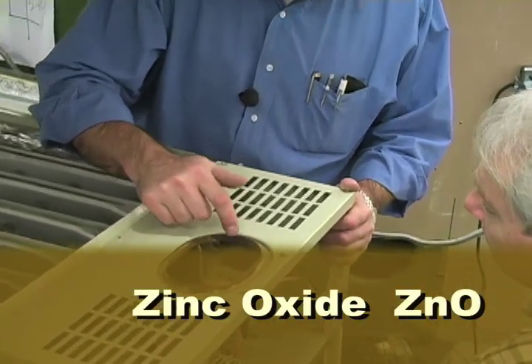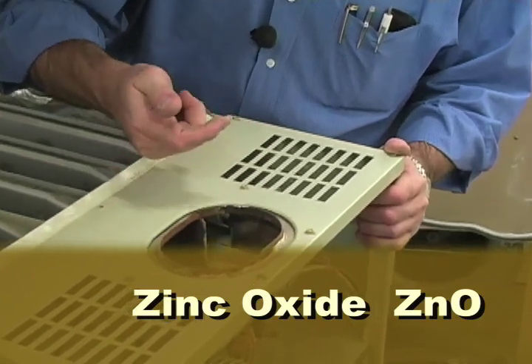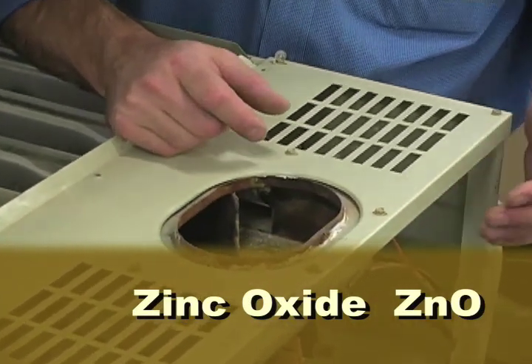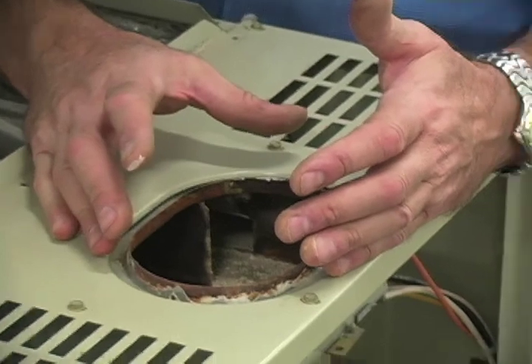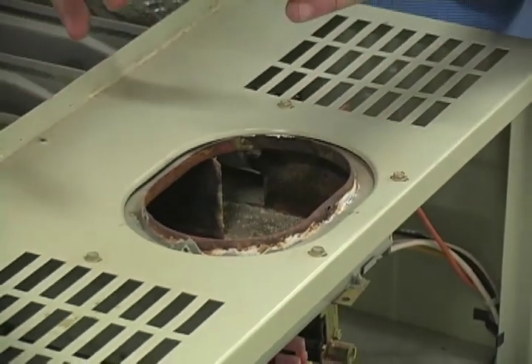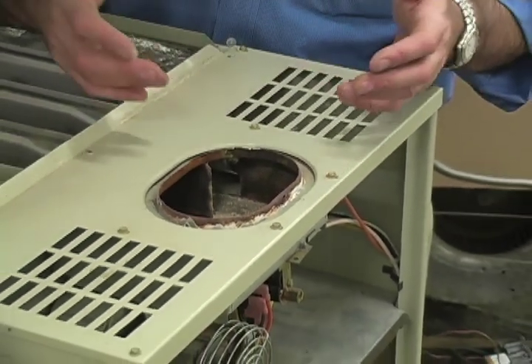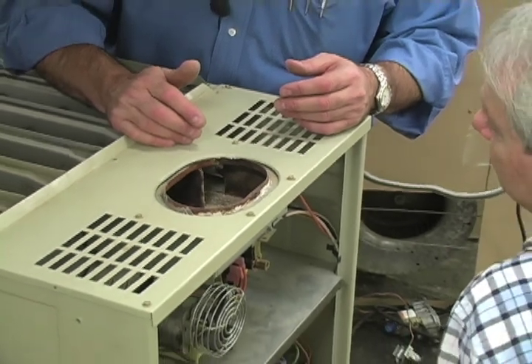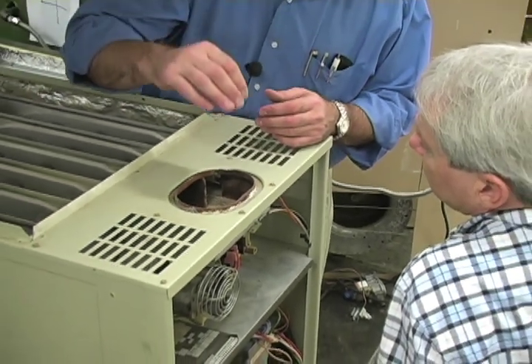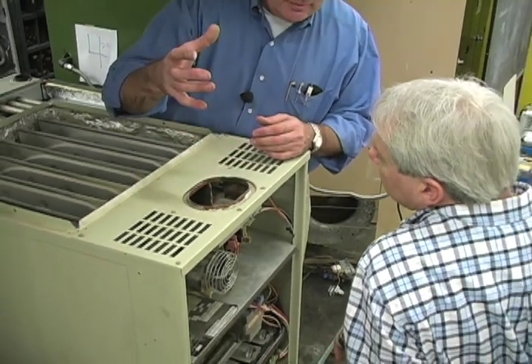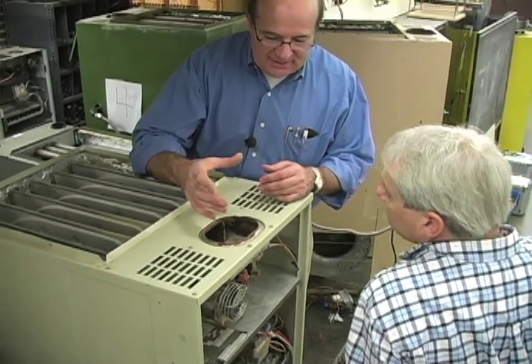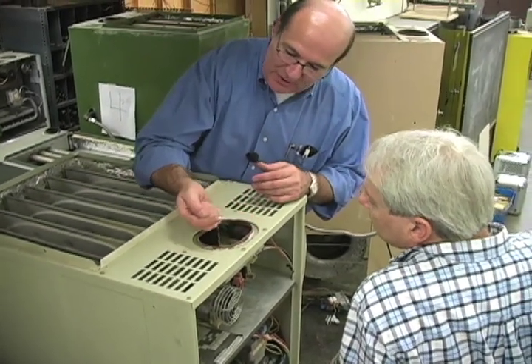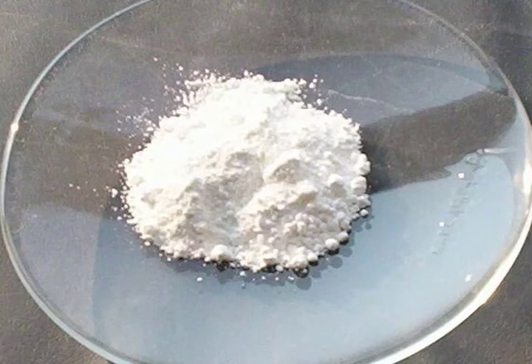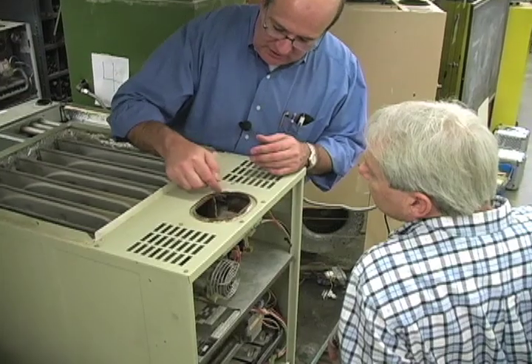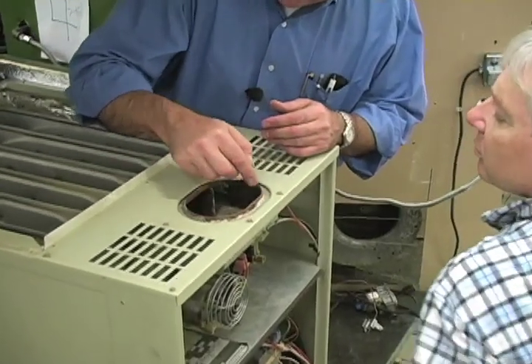And that galvanized metal pipe, if it's in a basement or someplace, is going to be a little bit cool. As the exhaust gas rises up out of the furnace, it starts cooling down. A lot of liquid inside that gas will start to condense back out. It probably ran down the inside of the pipe, started taking some of the zinc off the pipe, creating a zinc oxide, which is what this white powdery material is, and has started to corrode the collar on this furnace.